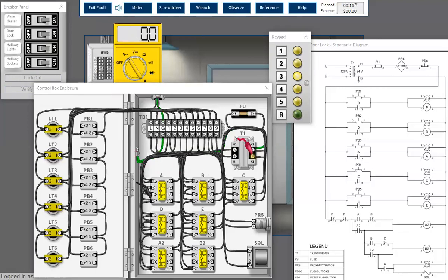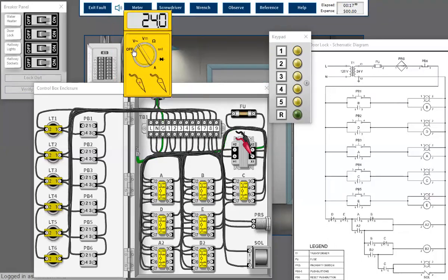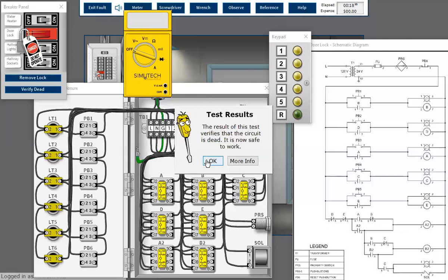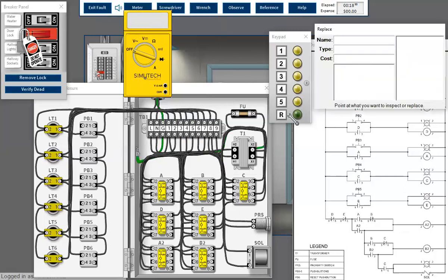So something is drawing it down. So what all should be, oh, you got a light, two relays, right? Three, relay A, LT3, and A2. Let me reset that and let's do one. So if I do one of them, it still pulls it down to 17. All right, only thing I can think of here is my transformer. Everything else I'm checking is looking good.